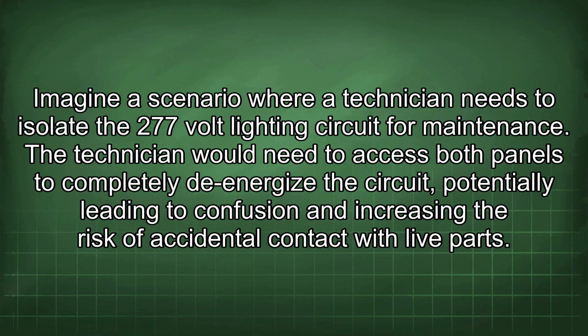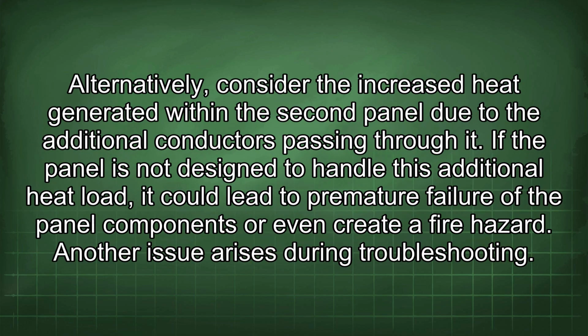Imagine a scenario where a technician needs to isolate the 277-volt lighting circuit for maintenance. The technician would need to access both panels to completely de-energize the circuit, potentially leading to confusion and increasing the risk of accidental contact with live parts. Alternatively, consider the increased heat generated within the second panel due to the additional conductors passing through it. If the panel is not designed to handle this additional heat load, it could lead to premature failure of the panel components or even create a fire hazard.